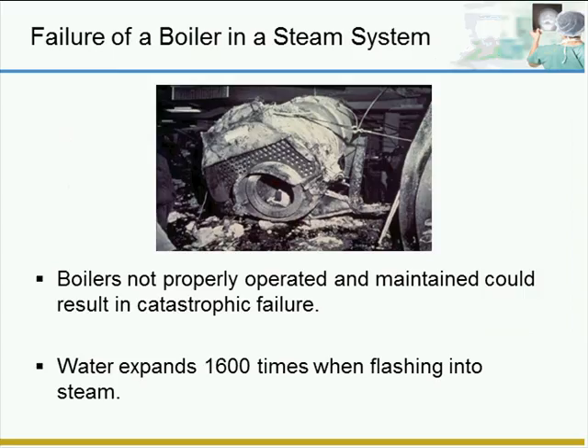The most severe boiler explosions are the result of a low water condition. The water level in the boiler will drop, the boiler will keep running, and when water enters the boiler, it'll flash into steam. Water expands 1,600 times in volume when it flashes into steam. This turns the boiler into a bomb. As you can see, this boiler had a low water condition, and that's the result. It's not a good situation.